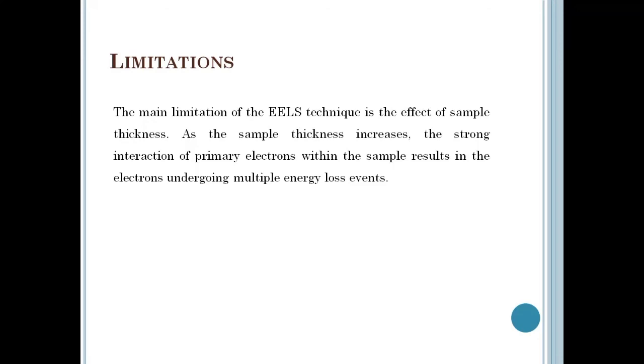The last part of this presentation is the limitations of the technique. The main limitation of EELS is the effect of sample thickness. As sample thickness increases, the strong interactions of primary electrons result in multiple energy loss events, which reduce the signal-to-background ratio of the EELS edges and reduce edge visibility. However, since the spatial resolution of TEM techniques is also reduced as thickness increases, the loss of edge visibility is not always the largest impediment to quality data. That concludes this presentation. Thank you for your attention.